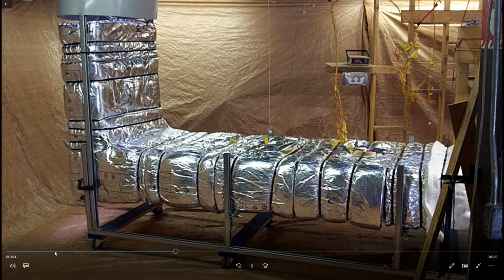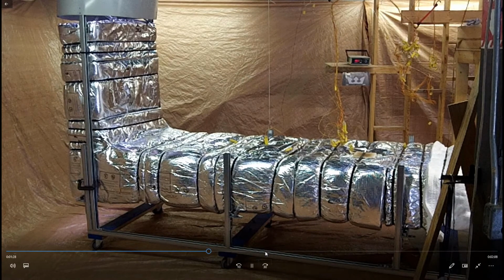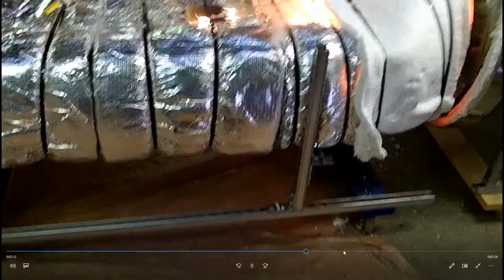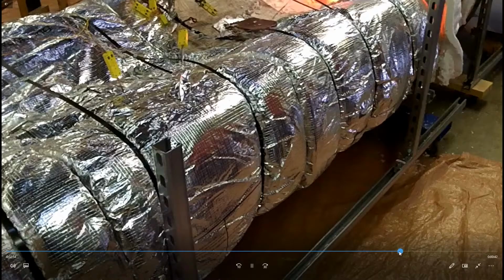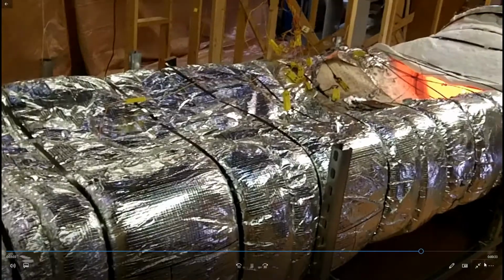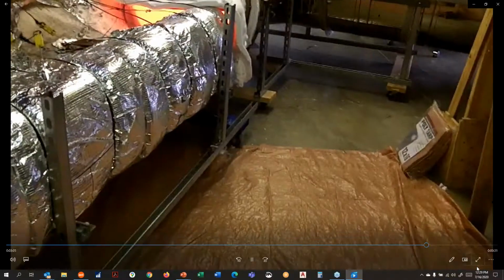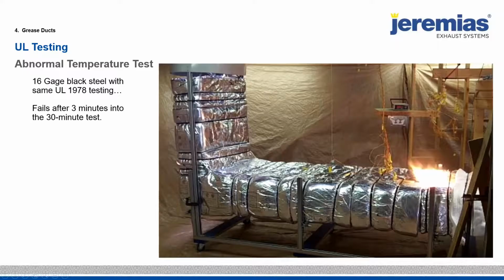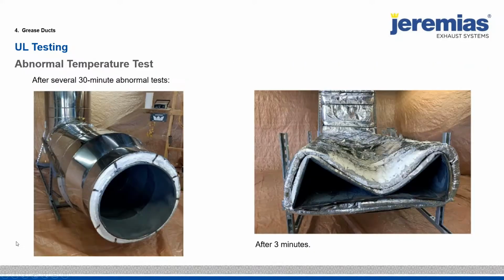So you have the ductwork that's collapsing very quickly, because what's carbon steel going to do at 2,000 degrees? It's basically melting. So we turned off the first test after 3 minutes, and this is why you see a lot of this information in our literature. On the left-hand side, you see a round system made of stainless steel. We've put this through maybe 11, 12 of these 30-minute tests. It just doesn't bother stainless steel, especially 444.